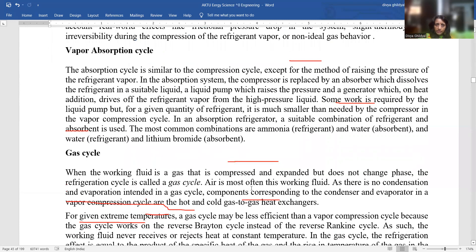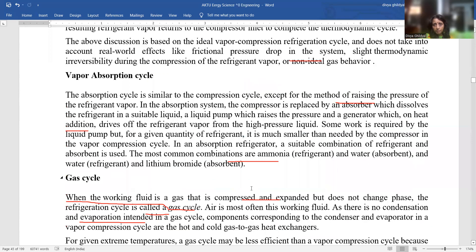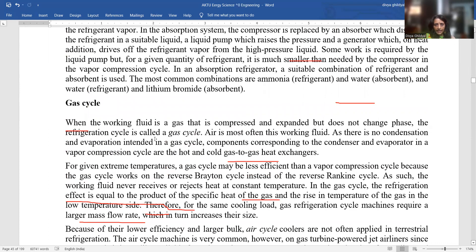Vapor absorption cycle: the absorption cycle is similar to the compression cycle, except in the method of raising the pressure of refrigerant vapor. In the absorption system, the compressor is replaced by an absorber which dissolves the refrigerant in a suitable liquid, a liquid pump which raises the pressure, and a generator which drives off the refrigerant on heat addition. Gas cycle: when the working fluid is a gas that is compressed and expanded but does not change phase, the refrigeration cycle is called a gas cycle. Air is most often the working fluid. There is no condensation and evaporation in the gas cycle.